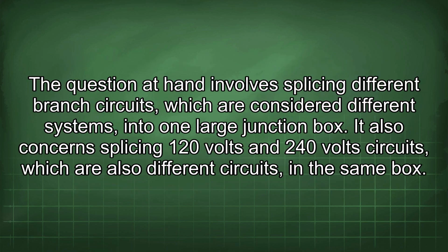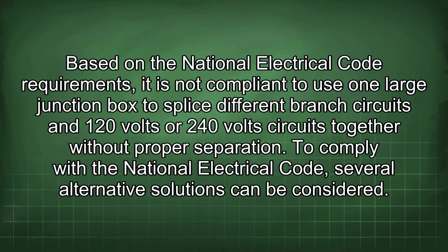The question at hand involves splicing different branch circuits, which are considered different systems, into one large junction box. It also concerns splicing 120 volt and 240 volt circuits, which are also different circuits, in the same box. Based on the National Electrical Code requirements, it is not compliant to use one large junction box to splice different branch circuits and 120 volt or 240 volt circuits together without proper separation.